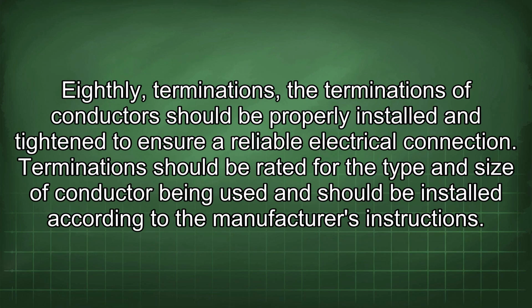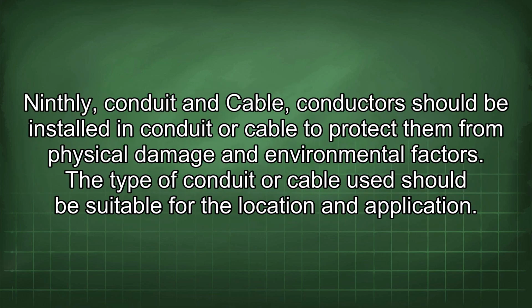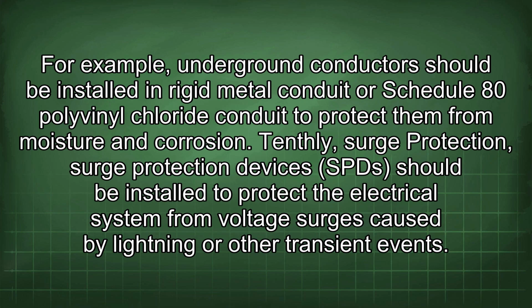Eighthly, terminations. The terminations of conductors should be properly installed and tightened to ensure a reliable electrical connection. Terminations should be rated for the type and size of conductor being used and should be installed according to the manufacturer's instructions. Ninthly, conduit and cable. Conductors should be installed in conduit or cable to protect them from physical damage and environmental factors. The type of conduit or cable used should be suitable for the location and application. For example, underground conductors should be installed in rigid metal conduit or Schedule 80 polyvinyl chloride conduit to protect them from moisture and corrosion.